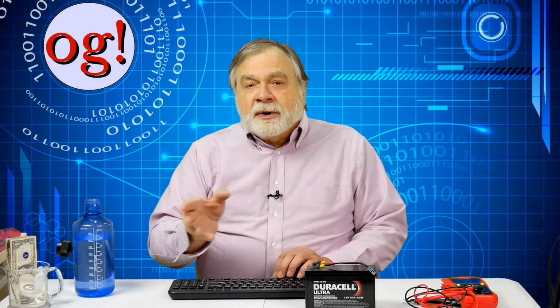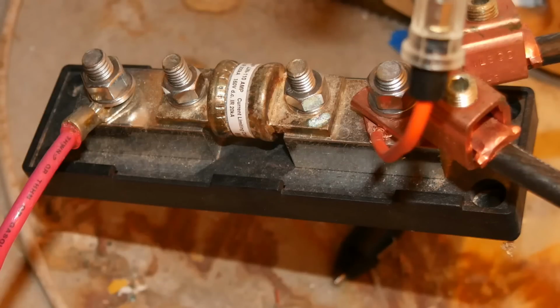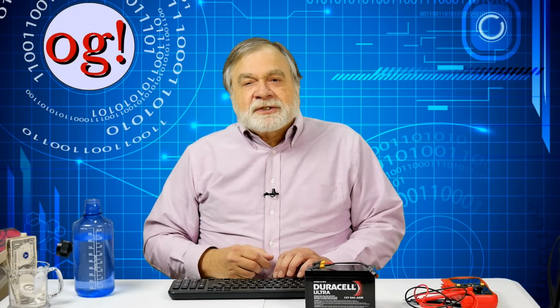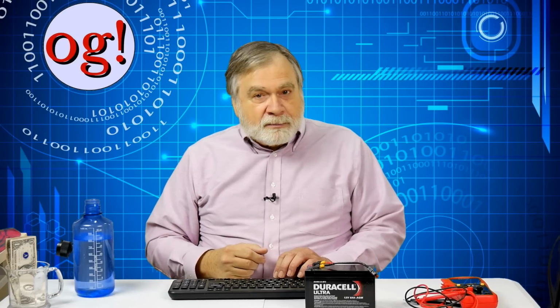Also, and this is extremely important, you need to put fuses everywhere. Even the battery should have one of these giant T-style fuses, and you need to make sure no metal falls on the batteries. The instantaneous discharge rate of a shorted battery is high, and a dropped wrench can turn to splashing molten metal in a heartbeat.